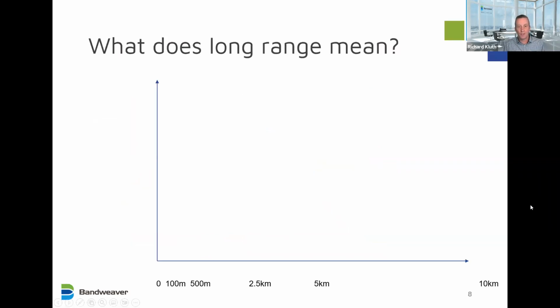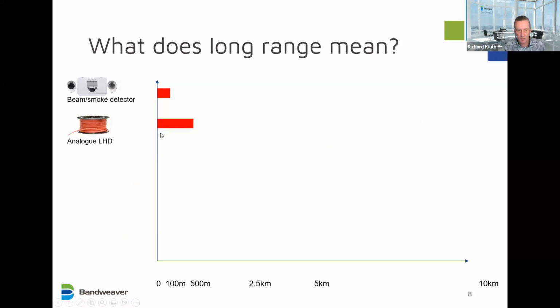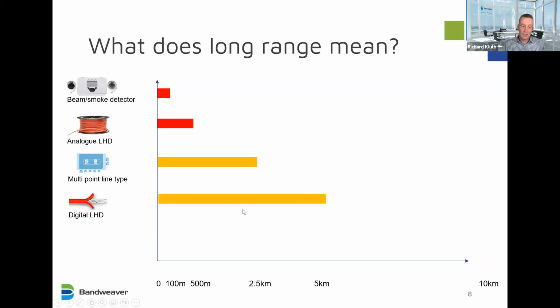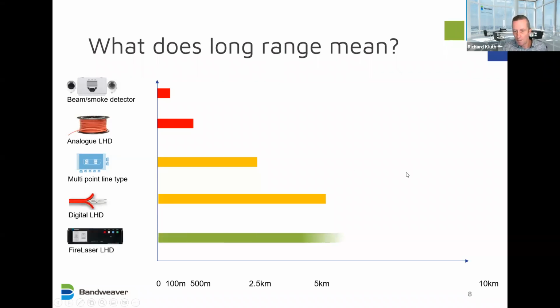So we've mentioned long range a few times. What do I mean by that? Let's look at a few different technologies so we can compare. A typical range for a smoke beam detector is around 100 meters. With analog copper-based linear heat detection, you can typically go about 500 meters between the panels. With multi-point line type detectors, we have multiple electronic sensors. You can get up to 2.5 kilometers, but with the limitation that the sensing points are spaced quite far apart. You have a maximum of about 250 per line, so sensing points can be more than 10 meters apart. Digital linear heat detection, again copper-based cables, can get up to 5 kilometers, which is entering long-range territory. But with fiber optic, you can go up to 10 kilometers with a FireLaser linear heat detection system.